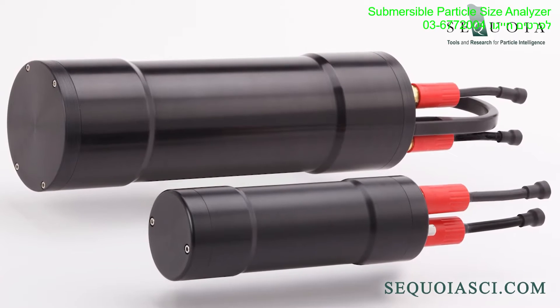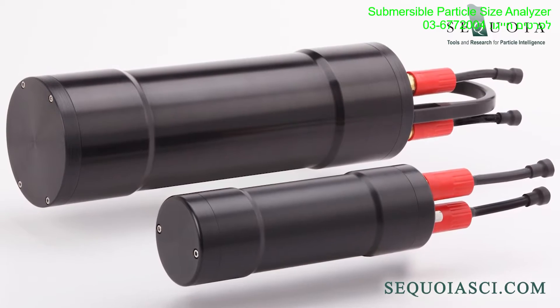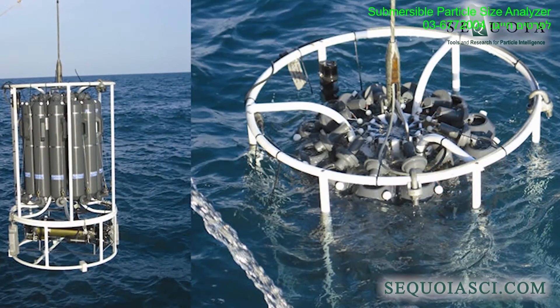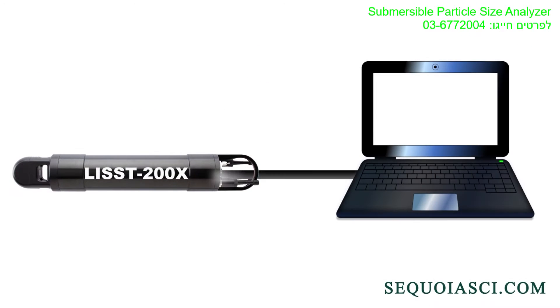First, the LISST-200X comes with an external battery pack, so the instrument can operate completely on its own. Just program it and secure it to a CTD or other profiling platform, or lower it on a rope in its deployment frame. When you have completed your profiling, offload the data and process them with the LISST-200X software to see the complete data.